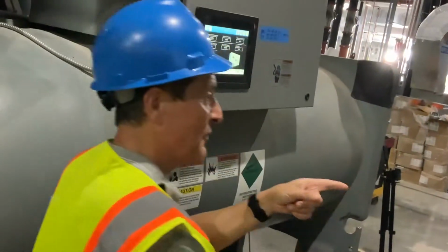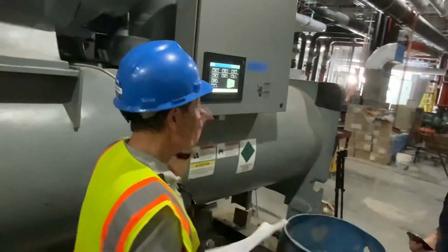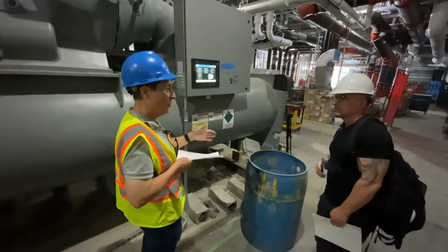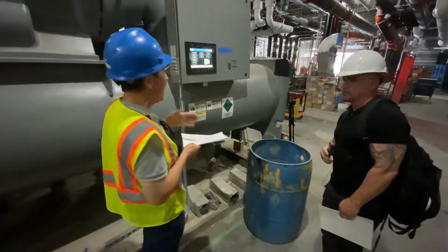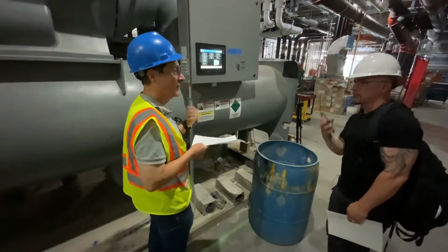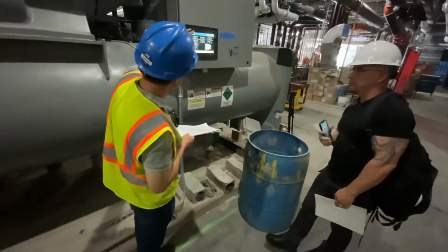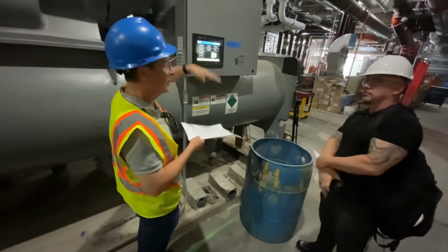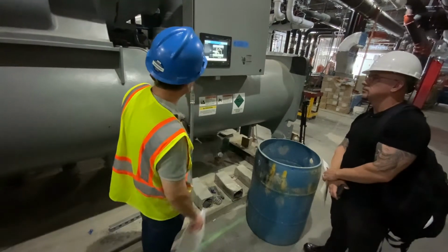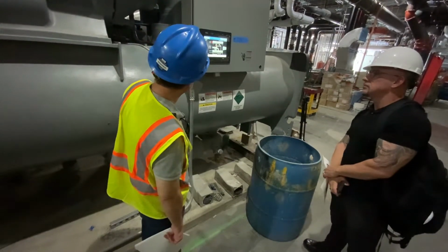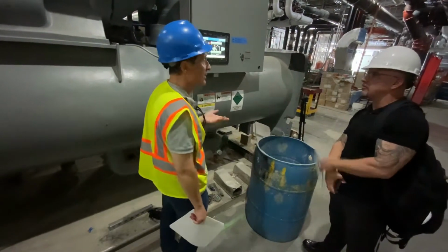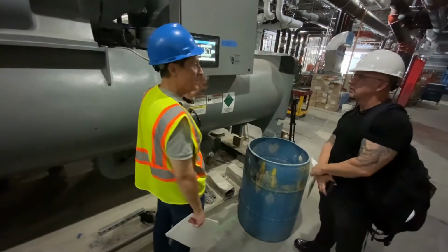I didn't finish the discussion when you started. Okay. So what happens is the inlet guide vanes are modulated and they can be controlled to the 42 degrees. They're regulating the amount of gas going into the first stage of the compressor. The VFD senses when there's less pressure differential between the cooler and the condenser. I think we'll start up some process. Either that or the heater just turned on. The heater will turn on and off as needed.